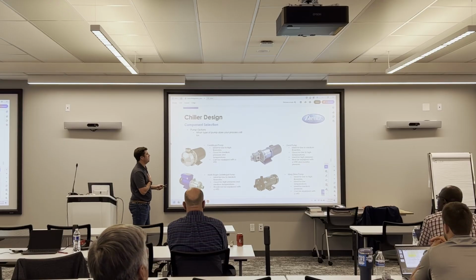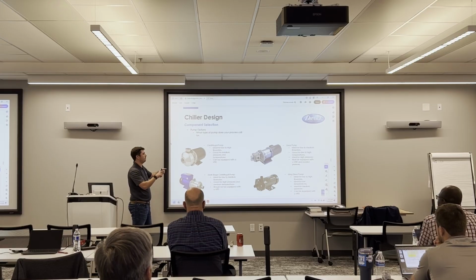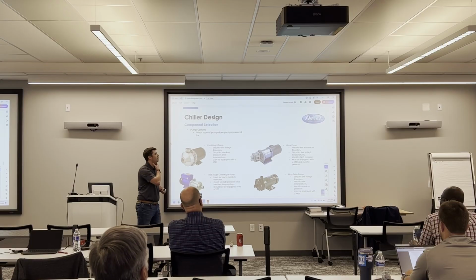A couple other options. We've got a gear pump. A gear pump doesn't really utilize an impeller. It actually just utilizes two gears to push the fluid through. I don't really have a graphic here. Just take my word for it. So it's ideal for low to medium flow rates. It's good for low to high temperatures, ideal for high pressure applications. Must be equipped with a VFD.